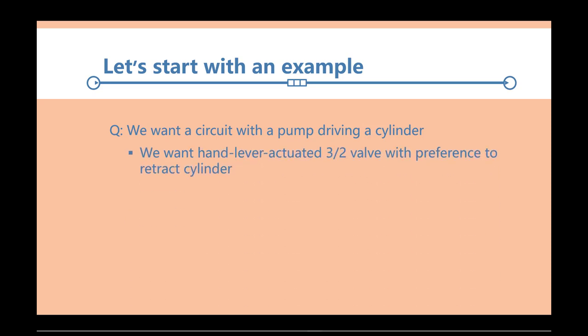And what we'd like to have is a hand lever actuated 3x2 valve with preference to retract the cylinder. So what 3x2 means is that you have three connections to the valve from external tubes coming into the valve, and the valve has two envelopes or two positions.